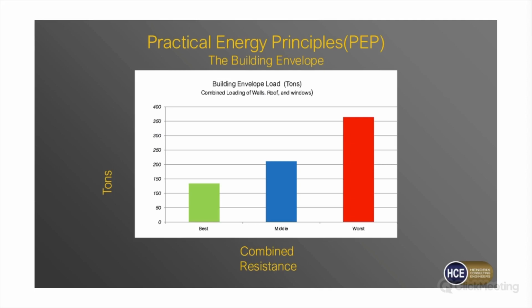If we're not willing to pay, and choose lower values for these systems, you can get up over 350 tons, maybe even push to 400. So it's easy to see you can more than double the load from your envelope alone, the load the AC has to work against every day, 24/7. These numbers don't go away like a variable people load does. So it's really important for our fixed asset that we make good decisions if we want to be energy efficient for the life of the building.